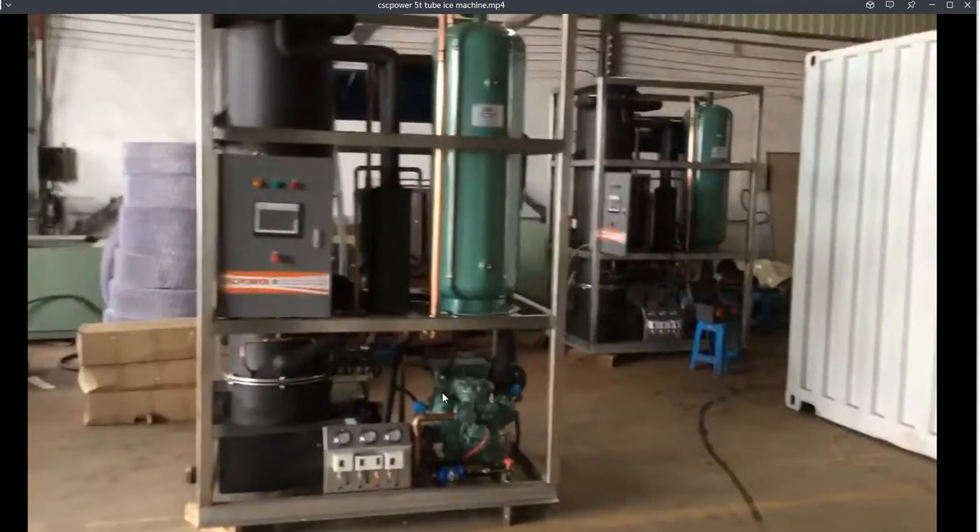We can clearly see that each machine is equipped with one 25-horsepower piston compressor. The compressor has six pistons — one, two, three, four, five, six. That is the 25-horsepower piston compressor. Clearly, CSC is using a 25-horsepower compressor for the 5-ton-per-day tube ice machine.